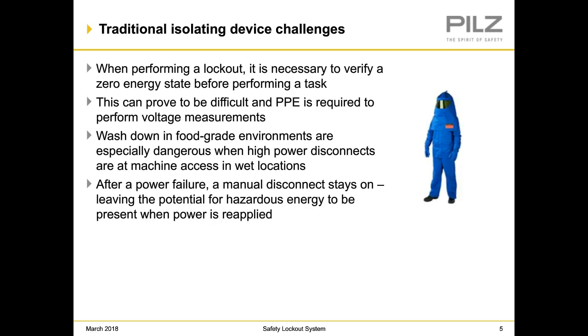Another traditional isolating device challenge to consider: when performing a lockout, it is necessary to verify a zero energy state before performing a task. This can prove difficult, and PPE is required to perform these voltage measurements. Washdown and food grade environments are especially dangerous when high power disconnects are at machine access points in wet locations. Also, you have to consider that after a power failure, a manual disconnect stays on, leaving the potential for hazardous energy to be present when power is reapplied.